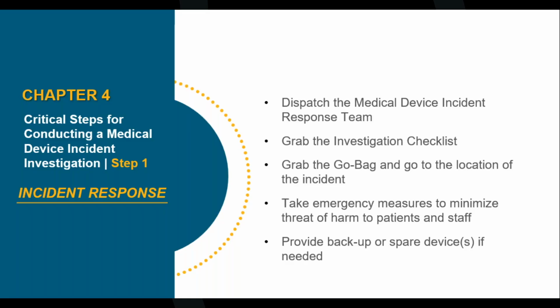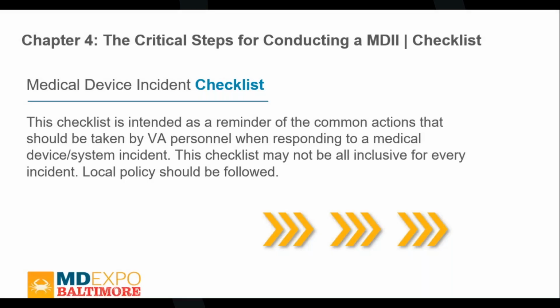And then take your measures to minimize the threat of harm to patients and staff, and obviously provide backups or spares if needed. We recently had an incident reported where a facility has 2 balloon pumps, and the one was not working in the middle of the case. They went to grab the other one, and guess what? It wasn't working either. It had some improper setup or wasn't set up correctly, and so they weren't able to use either. So we really need to make sure we have that backup equipment and that the backup equipment is working properly on a regular basis.